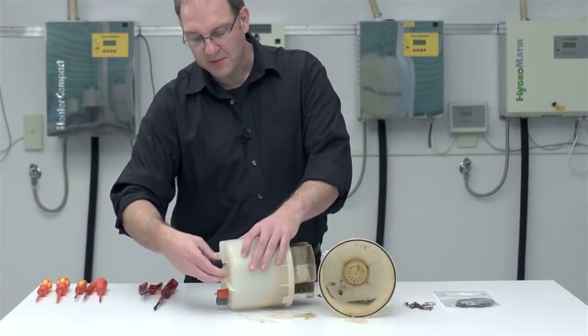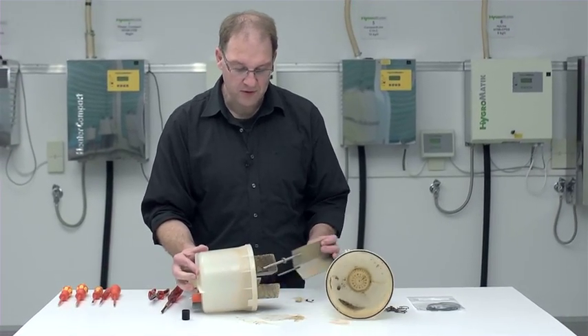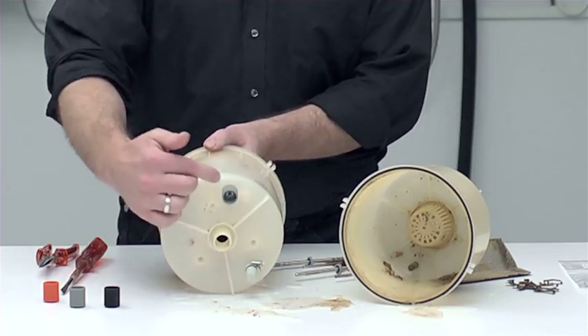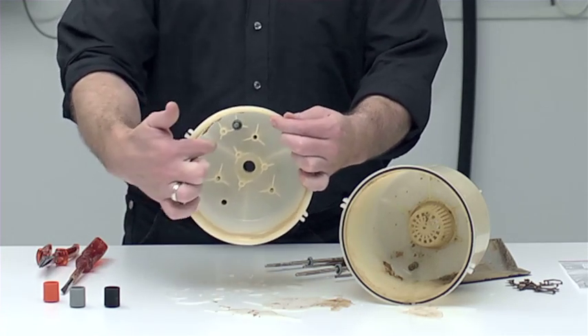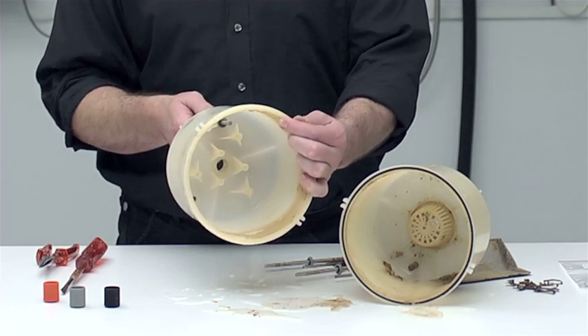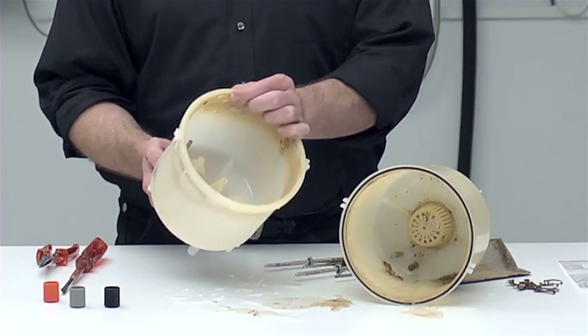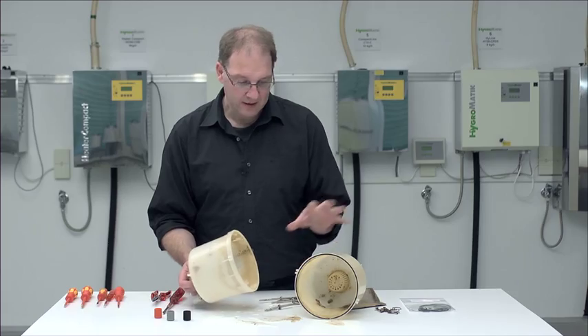This knurled nut can be loosened simply by manual force. Then press it to the front and you can see there is another one, which is the sensor electrode, a small metal pin that can determine the maximum level of water in the cylinder. This electrode does not wear down and does not need to be replaced, but you should disassemble it and include it in the cleaning.